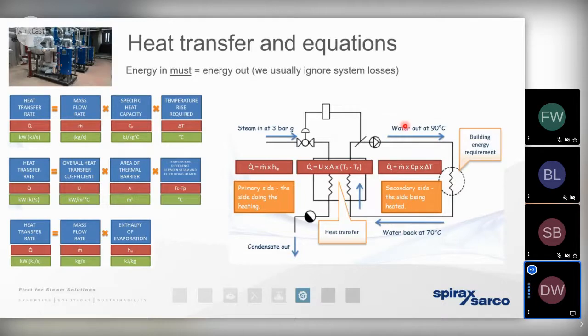In the case of the process example we're looking at here, we can see that we're adding energy to water, which we know has got a specific heat capacity of 4.19. And we can see that we need to add 20 degrees temperature to the process. So we simply multiply the mass flow rate by the specific heat capacity, by the temperature, and that helps us to determine the Q value, or the amount of energy we need to add to satisfy the process.